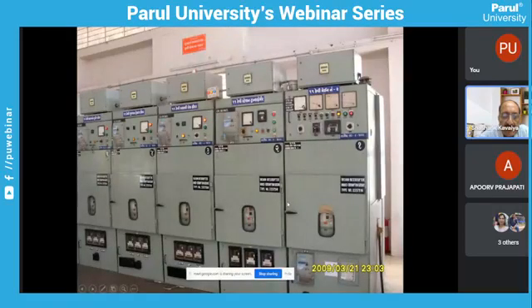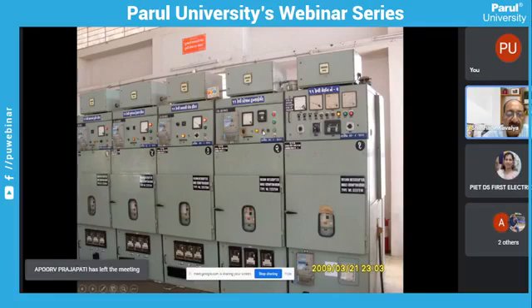See, the breaker just now. If you can see here, it is in out position. If the breaker is inside, this will be inside. I mean, it will be inserted. So when you are making the breaker in, you have to see that our DC is on. DC circuit is on. Then by pushing this button, you will find that the trip circuit is healthy. You have to check every time the trip circuit should be healthy. If the trip circuit is not healthy, then if there is some problem, the breaker will not trip, and if the breaker does not trip, it will blast. It will not only blast, it will damage all the panels.